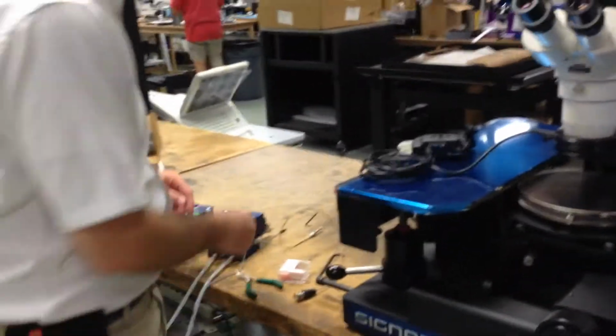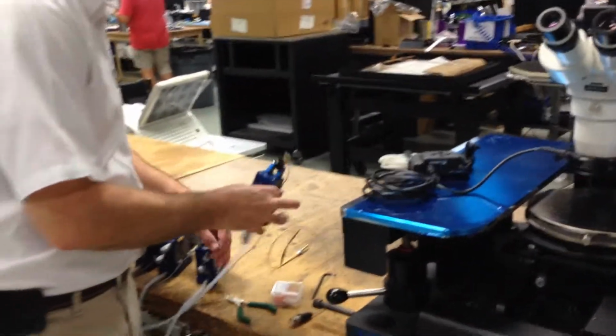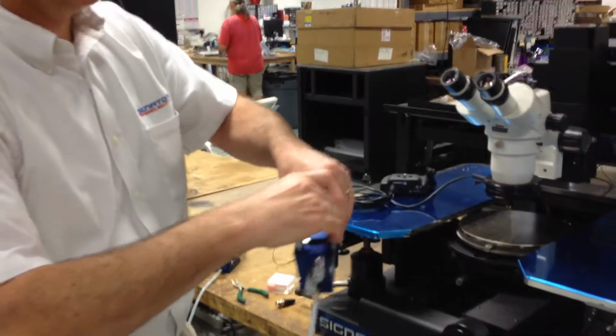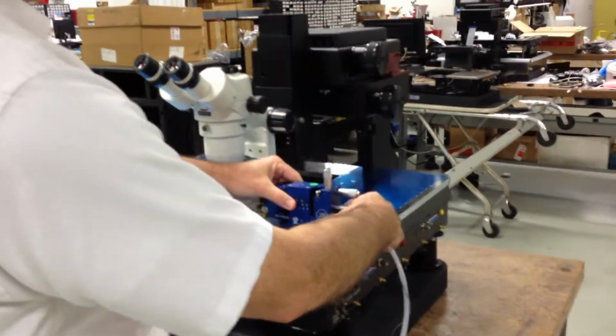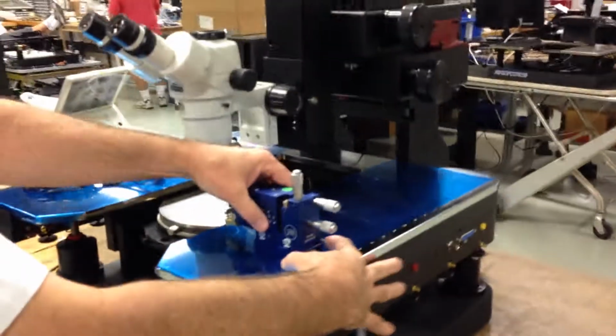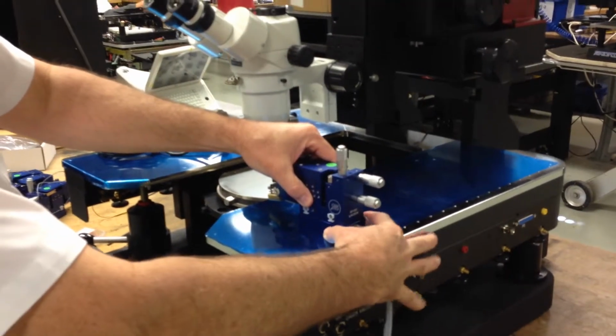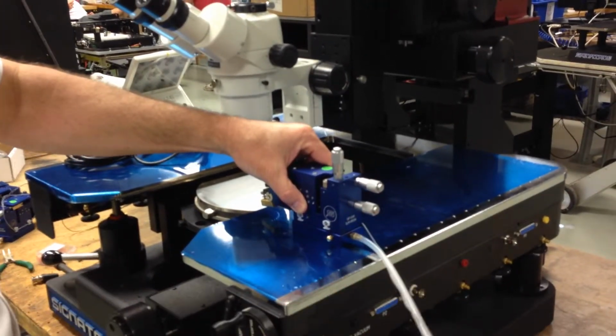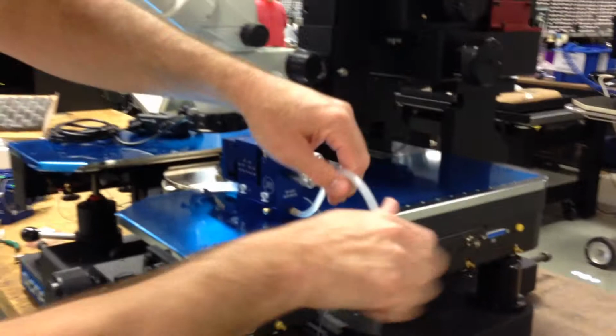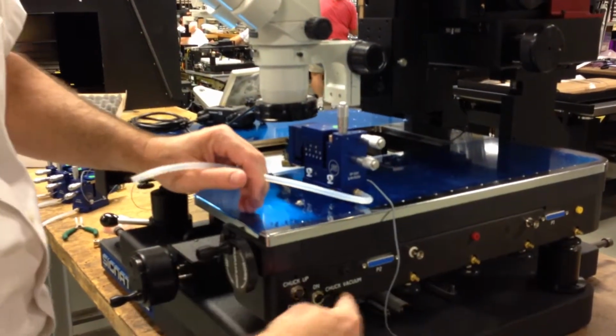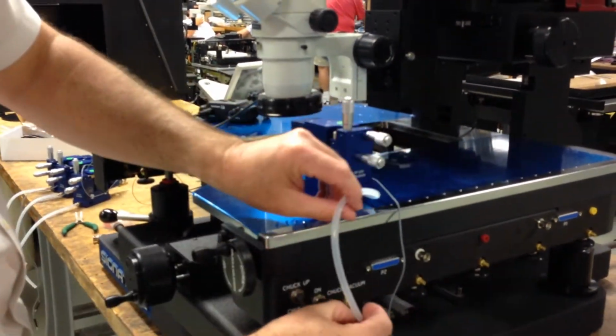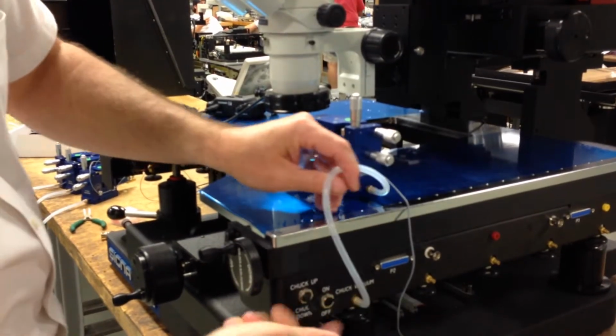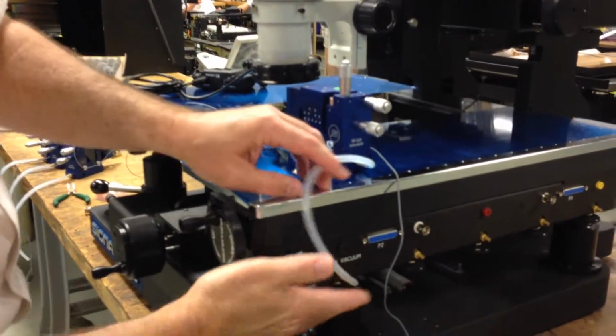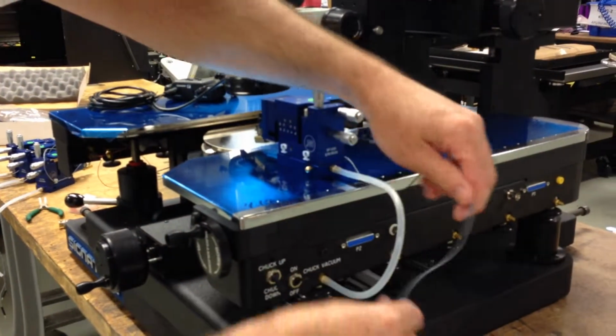Next we'll set up a micropositioner and probe. The micropositioner sets on the platen. This is a vacuum base. The vacuum is released by this button here on the side. You set it on there. The vacuum tube obviously connects to any one of the vacuum ports here. And then the vacuum intensity is controlled by the knob here. And this is the electrical connection here.